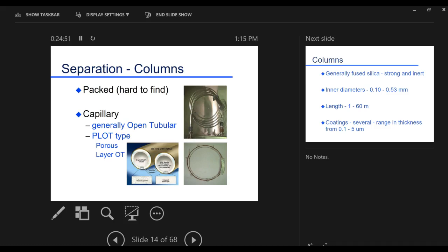Well, that was a nice idea, but it really wasn't theoretically very sound. And so over time, we've progressed to use a capillary column. This column replaces that packed column. It is going to be 0.25 millimeters, a quarter of a millimeter, in diameter. And it's going to be 30 meters long, 15 to 100 meters actually. So I've got this tremendously long column of a very, very tiny diameter. There's no packing inside of it. It's completely open. It's an open tube.